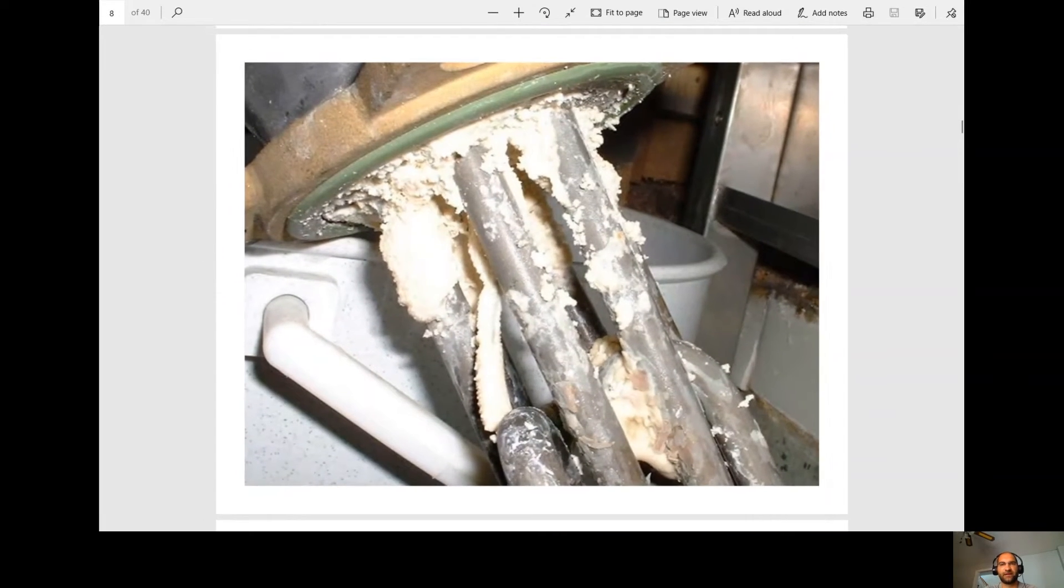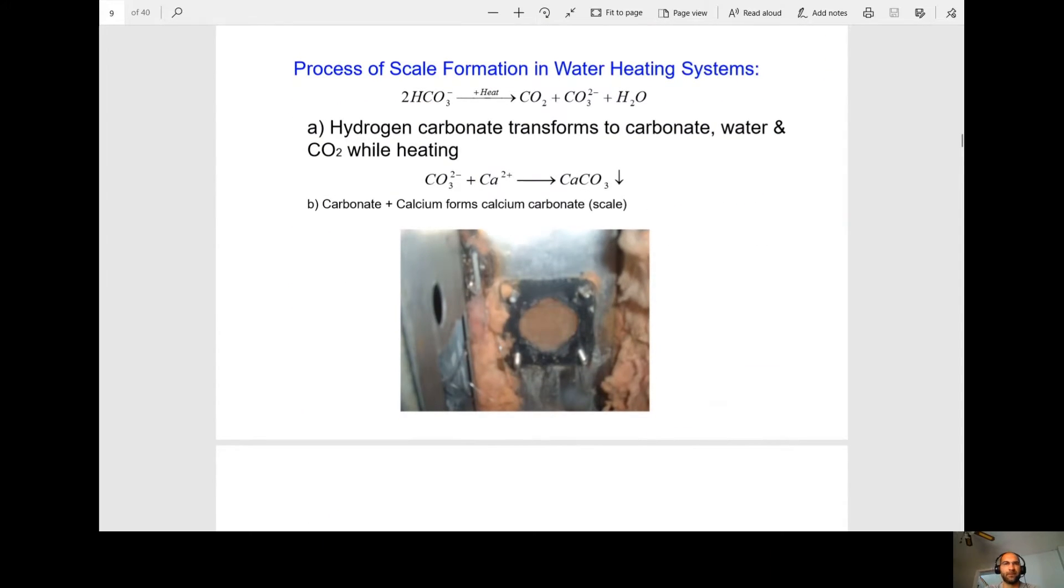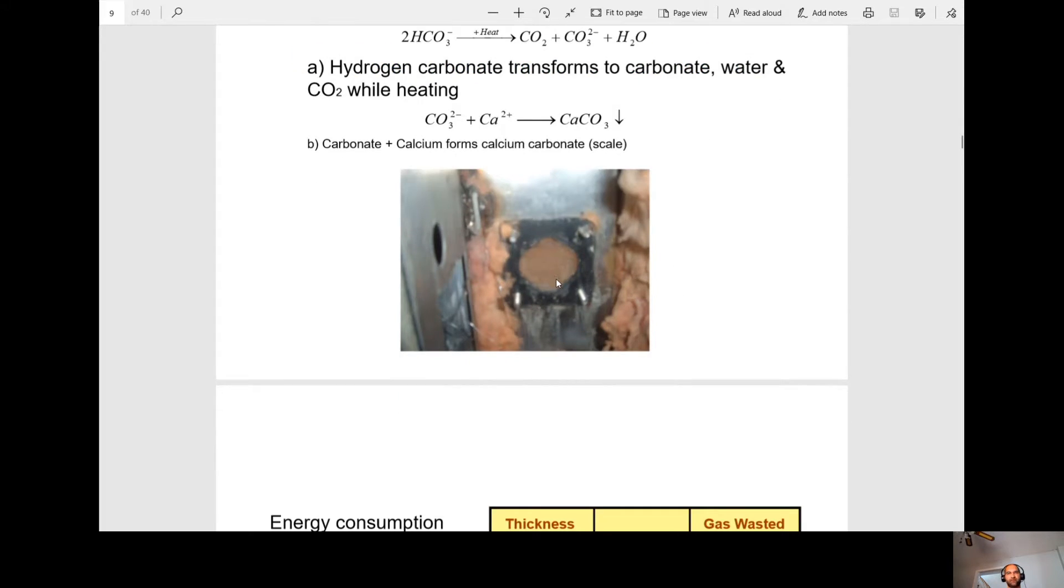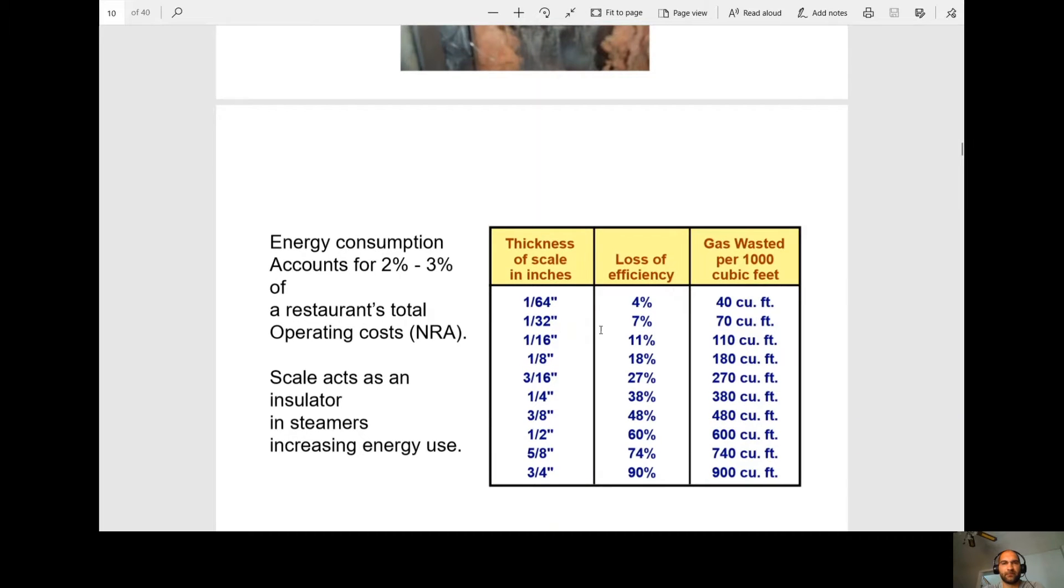Here's just an example of scale buildup. Basically what happens, how we build scale is hydrogen carbonate transforms to carbonate and water CO2 while it's heating. Carbonate plus calcium forms calcium carbonate, which is scale. As we can see, this one's really bad. We can't even see through here, through this access port, check our water level probes. This is probably through the secondary low water cutoff.